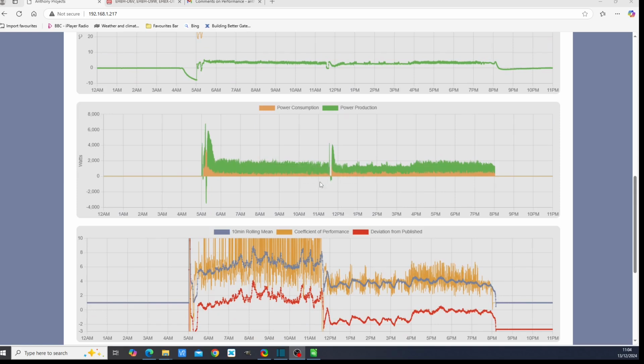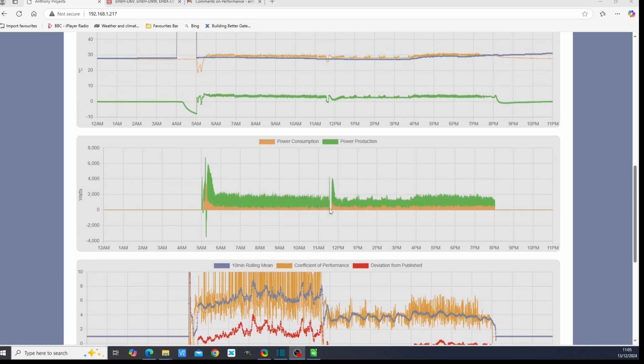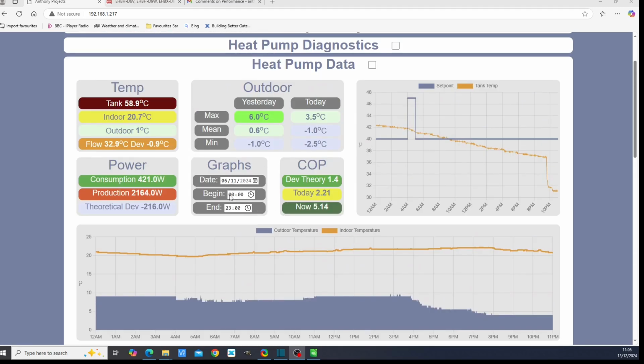So what we're going to do is look to see why we were getting such good coefficients of performance beforehand, COP of about 6, and why we were getting such a terrible coefficient of performance. COP was going down to about 3 in many instances after the heat pump came back on. So we'll zoom into this range here, 11 till 12.